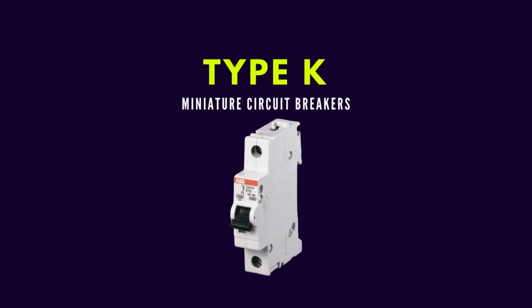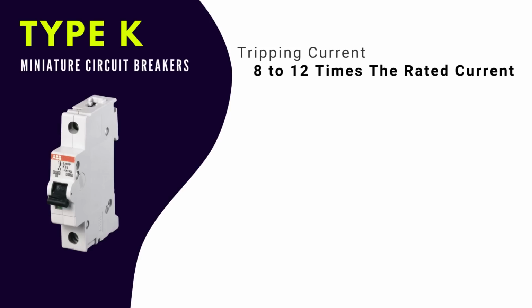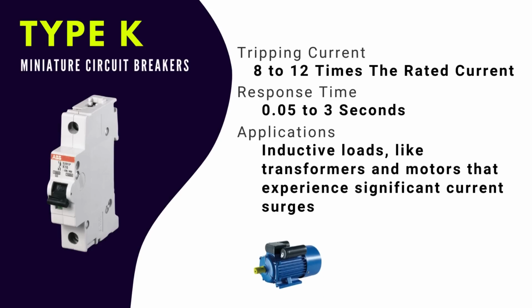Next is the Type K MCB, which trips at 8 to 12 times the rated current. It's designed for circuits with inductive loads, like transformers and motors that experience significant current surges. The tripping time for Type K is between 0.05 and 3 seconds, ensuring protection while accommodating those high inrush currents.